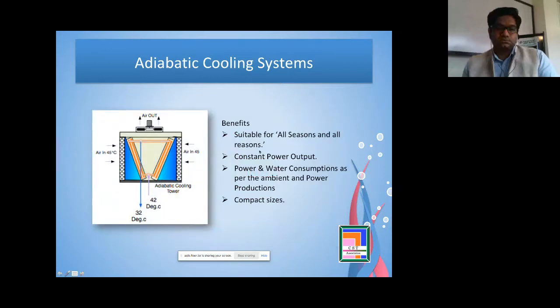So my slogan for adiabatic cooling towers is, see, this is suitable for all seasons and all reasons. All seasons means when our ambient goes lower, we save energy on the fans. When the ambient temperature is equal to the approach temperature, it still saves the water. When the ambient temperature goes higher, it sprays the water and then it saves the water. Sorry, it saves the water as compared to the cooling tower, and it also saves the fan power. This is for all seasons.